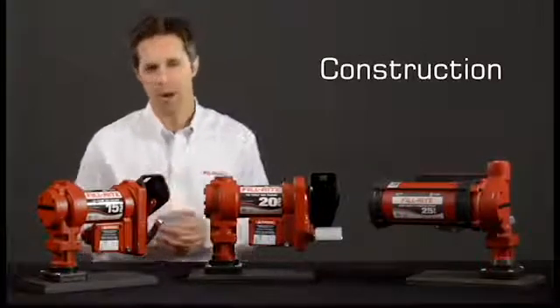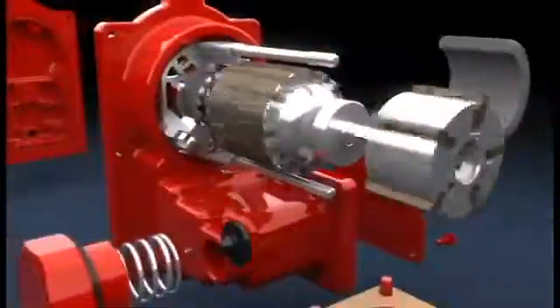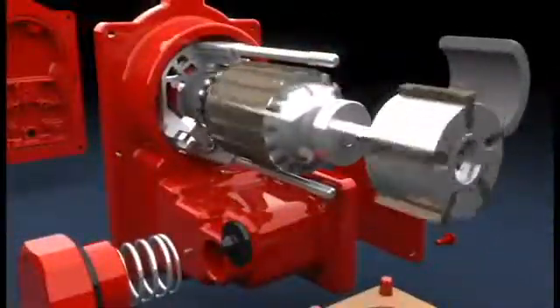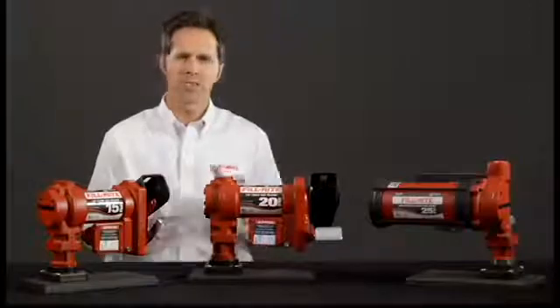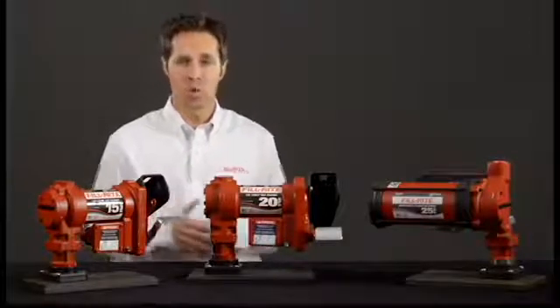Just about all Fill-Rite pumps are a rotary vane design. Inside the pump housing, a powdered iron rotor is attached to the end of a motor shaft and turns a set of sintered bronze vanes. This design is important because flow does not drop off as the vanes wear — they simply slide further out of the slots in the rotor.